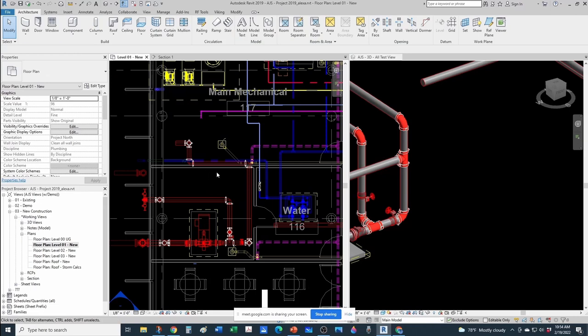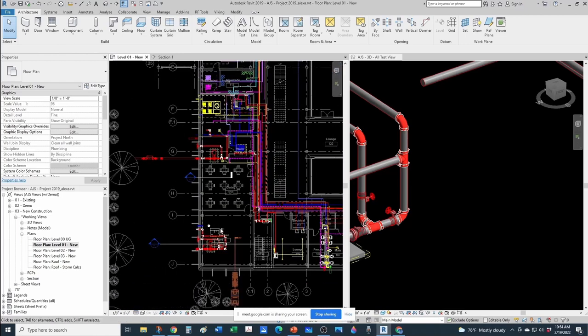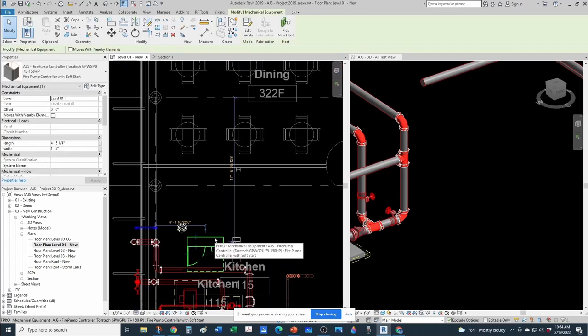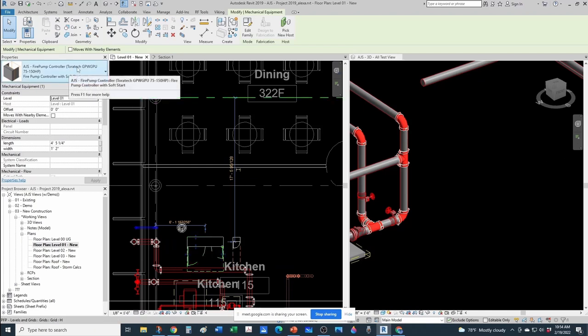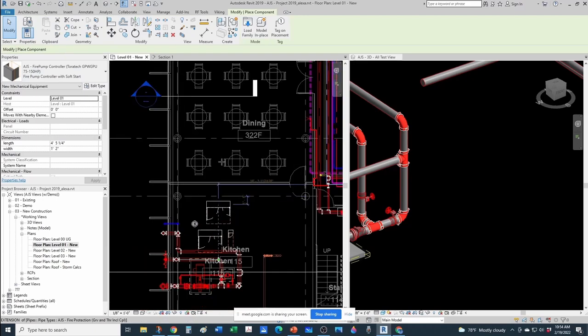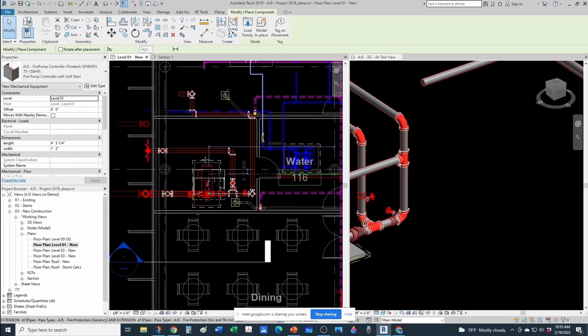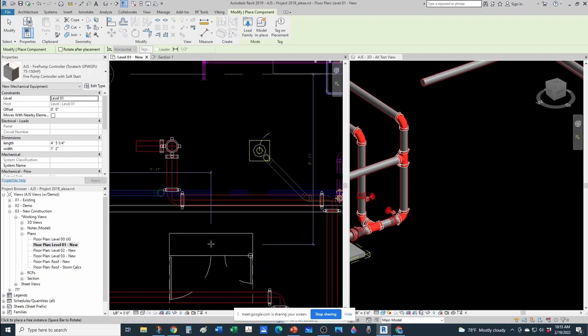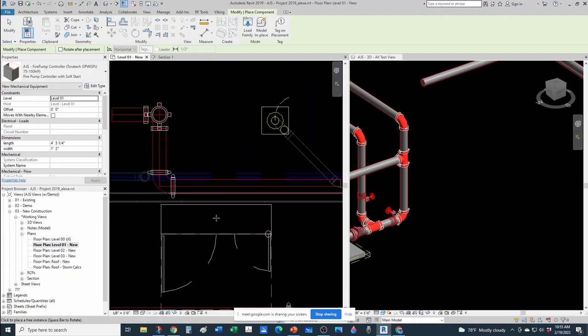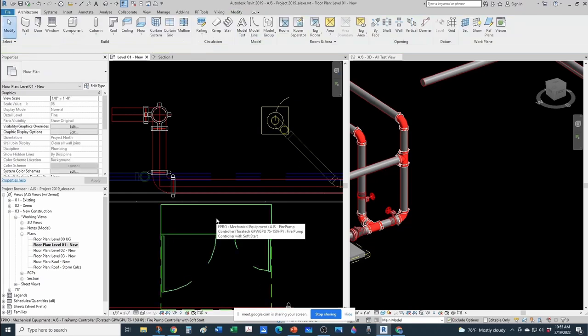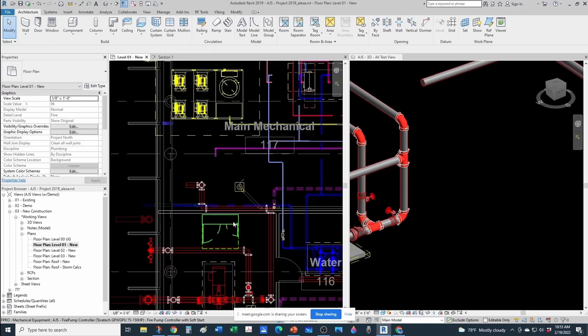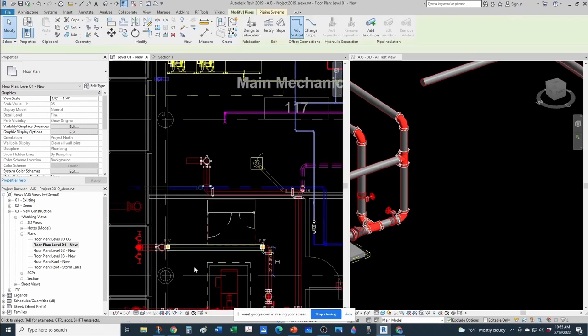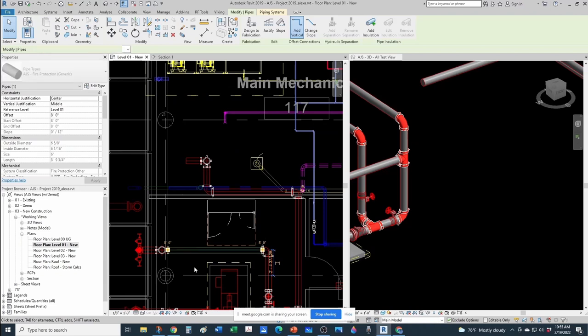Now we need to have a fire pump controller here, and then we'll adjust our fire department connection line here. So for pump controllers, you know, you can go with Firetrol. In this case, this one's a Tornatech. The only thing important is that you make sure that it can handle your fire pump horsepower. It has the correct IEC rating, and if you are using an automatic transfer switch, just make sure you include that in your specs, of course. Let me take this a little bit closer to my pump. Oh, and we're missing our jockey pump as well. We need to provide that one.